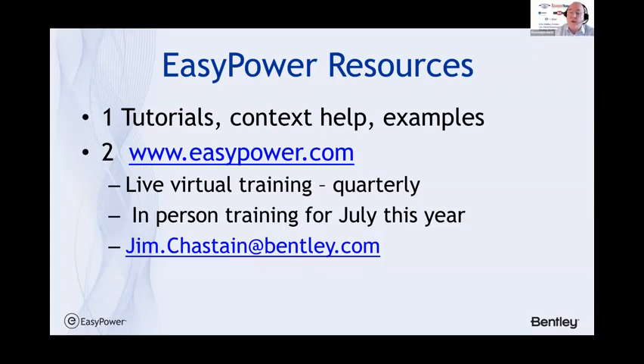Okay. We are working on a project with both utility and, through an ATS connection, generator backup. What is better, 2 separate labels or 1 label with both ratings? It depends if you're going to have maintenance under either condition or both conditions. What's ironic is that the generator supply is usually more dangerous because the currents are lower than the utility, and the lower current means a slower response time for the protective devices. So I'd go with 2 labels, if I have maintenance during both periods.